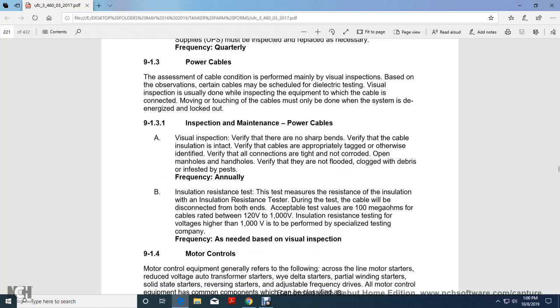Power cable. The assessment of cable condition is performed mainly by visual inspection, based on observations which may be followed by dielectric testing. Visual inspection is usually done by inspecting the equipment to which the cable is connected. Moving or touching the cables must also be done with the system de-energized or locked out. Inspection for the maintenance of the power cable.